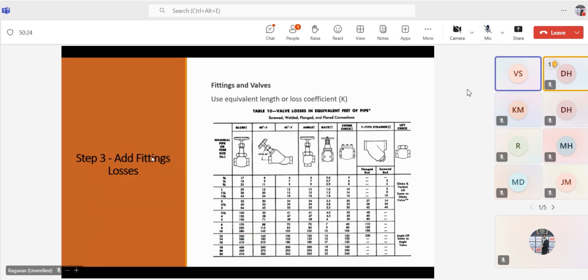Okay, so the next slide, pipe and valves fittings. Calculate the equivalent pipe length for the fittings and valve losses using the ASHRAE guideline or manufacturer data sheet. So you can get it from here, all the data is there. You can see the valves and everything, and corresponding pipe sizes on the left side. Based on that, you can get the equivalent length. Then once you get this value, you can put it in the Hazen-Williams equation, and you will get the pressure drop of each pipe and fitting, sorry, the valves and fitting losses. Can you move on to the next slide?